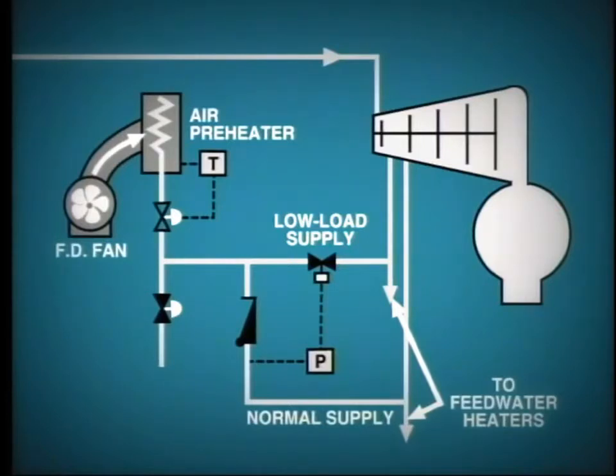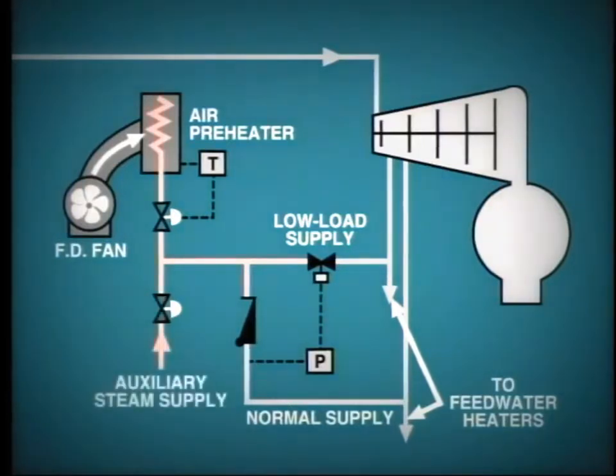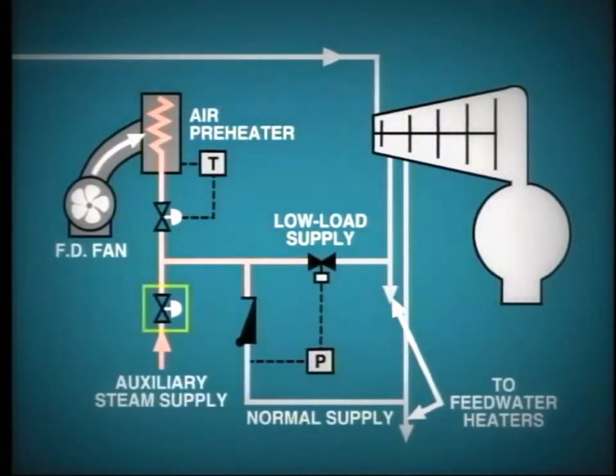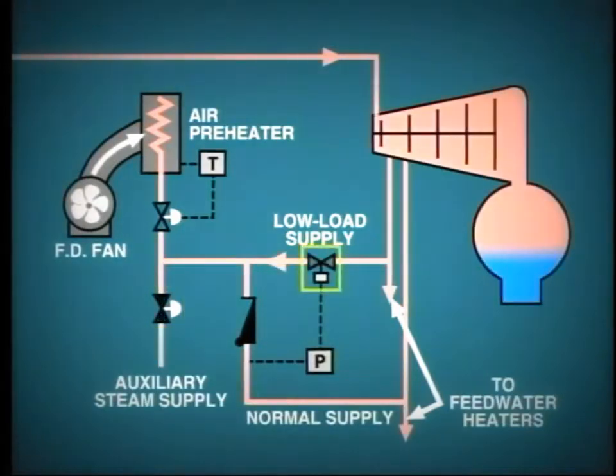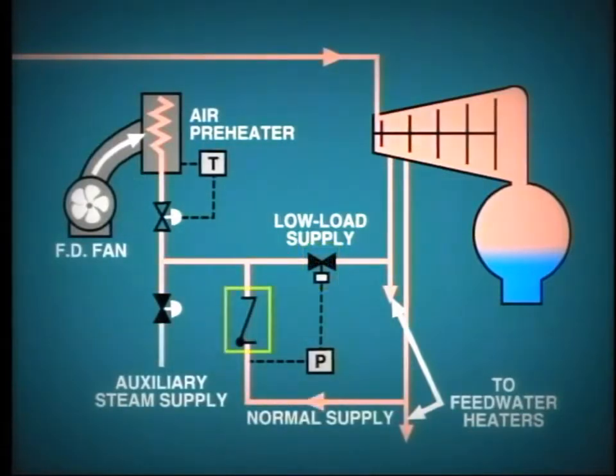In this case, a third supply of steam is available from the auxiliary steam system. Each of these control valves automatically opens in the correct sequence: one, the auxiliary steam supply during startup; two, the first stage steam extraction during low load; and three, the second stage steam extraction at high load.